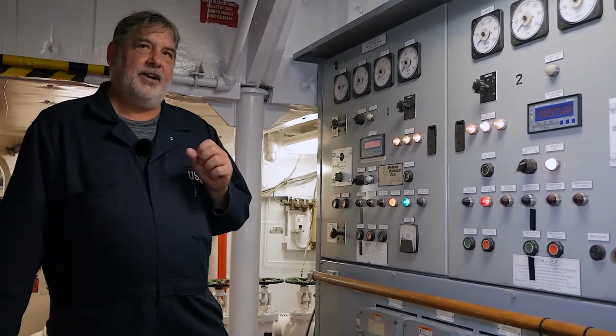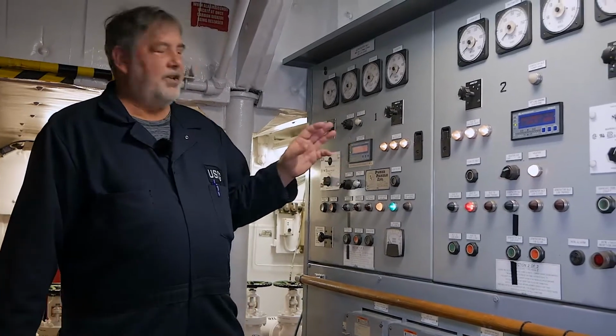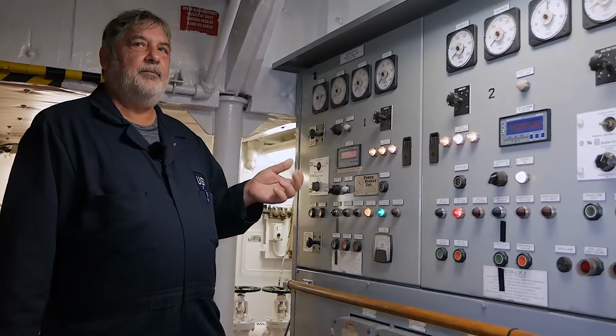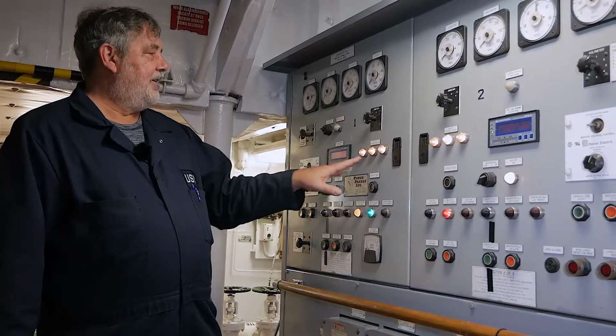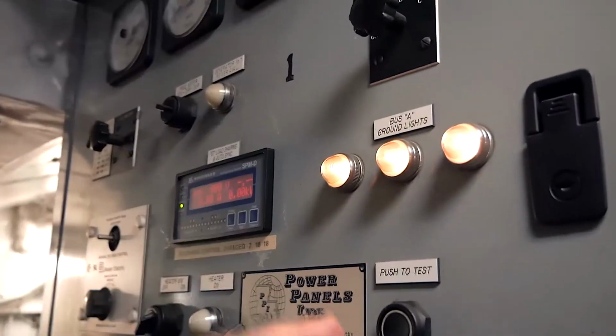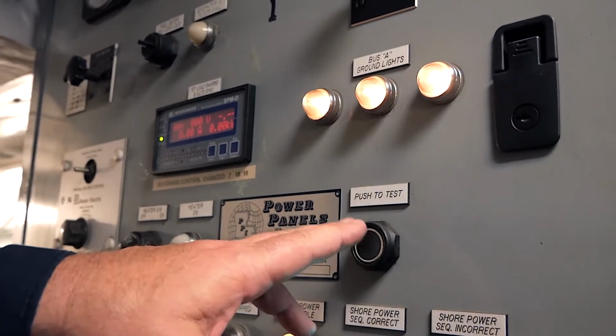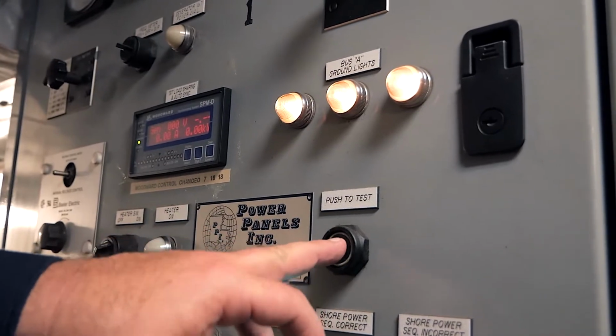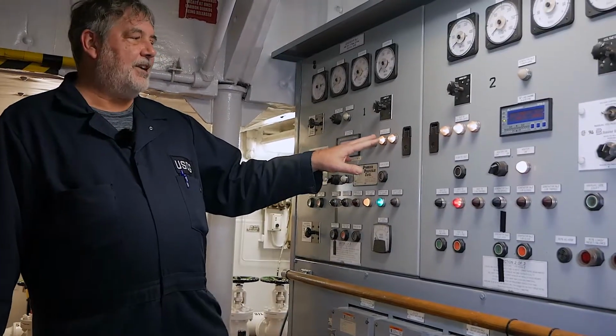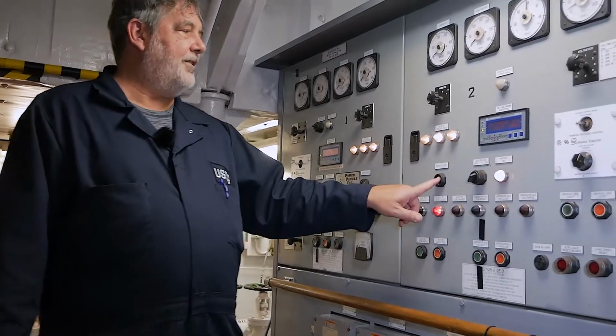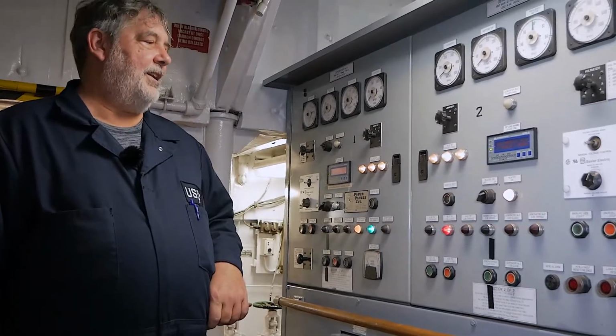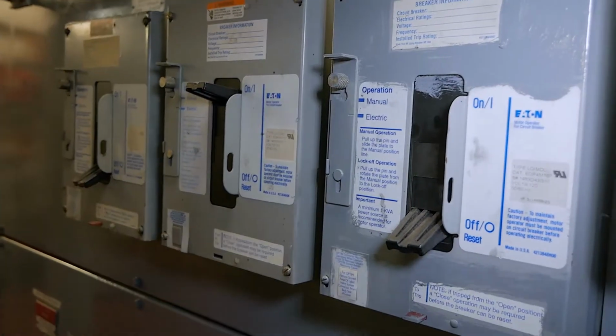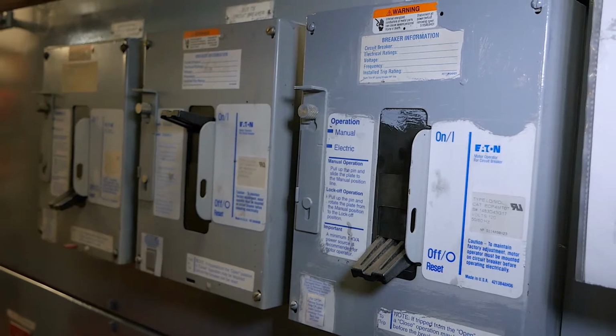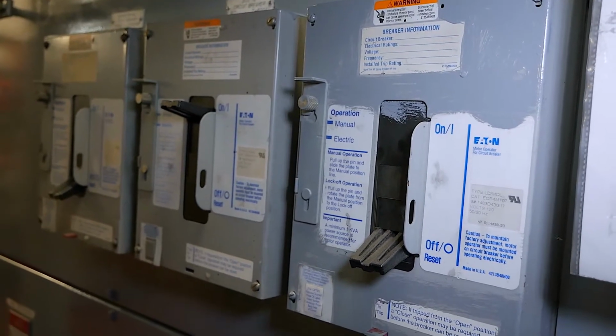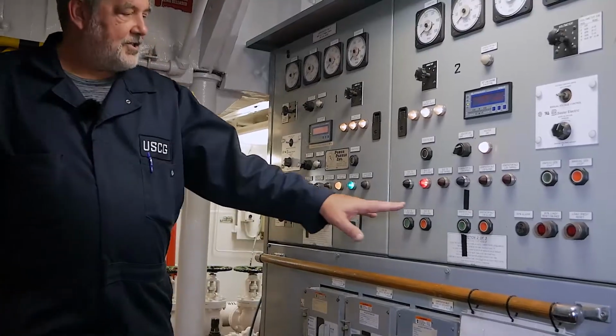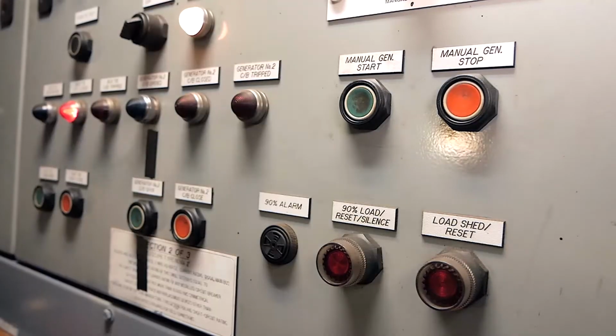The passive ground detectors are the ones that require action from me before it will indicate a ground. Here's your 3 lights and the push button that most folks are used to. I push the button and see that the lights stay lit, therefore no ground is indicated. All the circuit breakers that are installed are labeled properly, and the start and stop controls for the engines themselves.